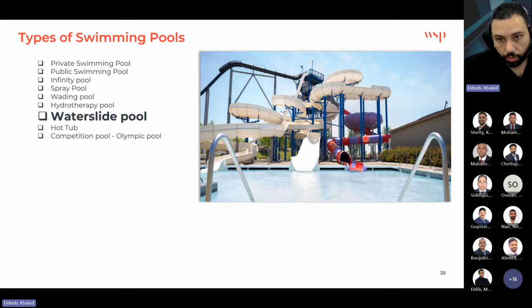This is to make sure that the water flow in the slide is constant and reliable, to avoid dangerous situations like insufficient flow, which causes friction burns, or the slides being slow. So imagine if we are playing, enjoying, and then the pump stops because the designer connected it to the filtration system. This would be a very bad situation.